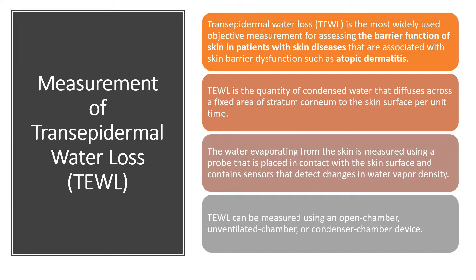The water vapor evaporating from the skin is measured using a probe, similar to the corneometer. The probe is applied to the skin and allowed to detect for 30 seconds to one minute, and the readings are recorded on a monitor using software. The same process applies to TEWL devices — the probe is placed on the skin, detects the value, and the result is calculated and displayed on the monitor.